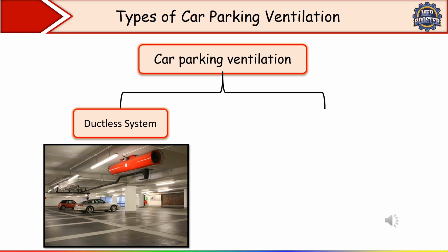Now remember, using a car park ventilation system with jet fans eliminates the need for bulky ductwork, okay. Not only does this result in saving on materials and space, but also in considerable saving in operational cost as the result of lower power consumption of the axial fan, by eliminating the ductwork in combination with a well designed control system.